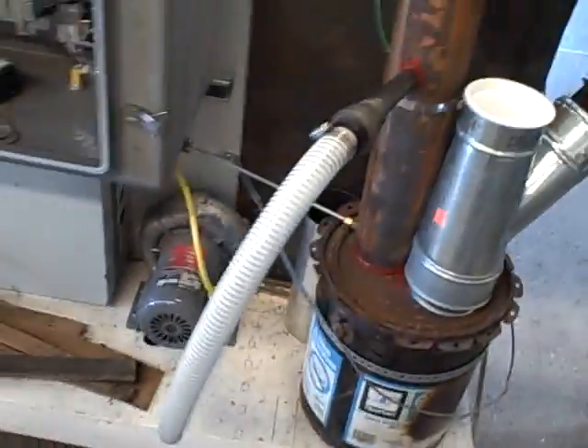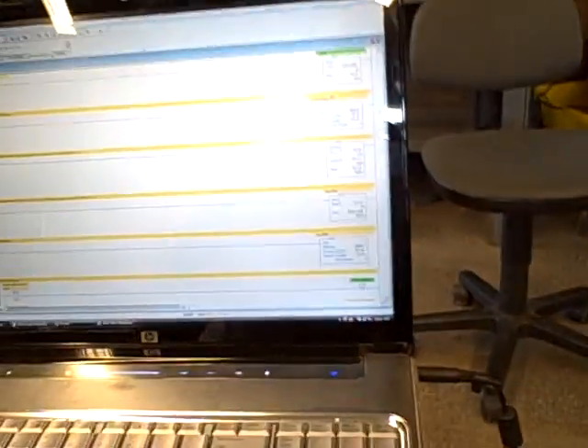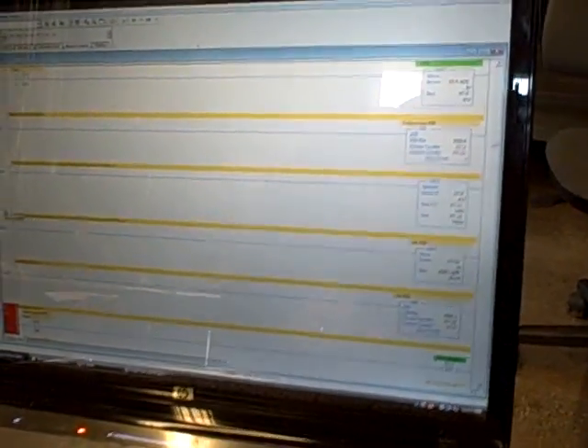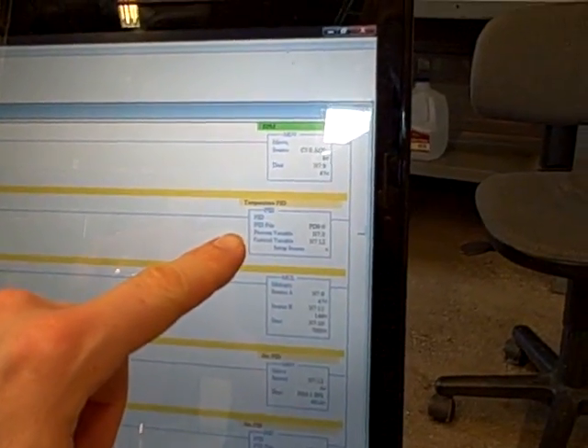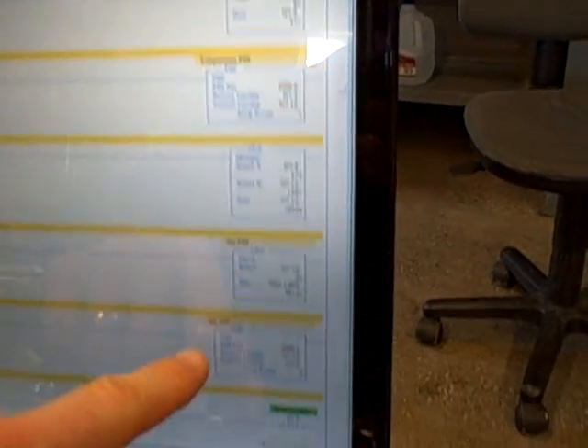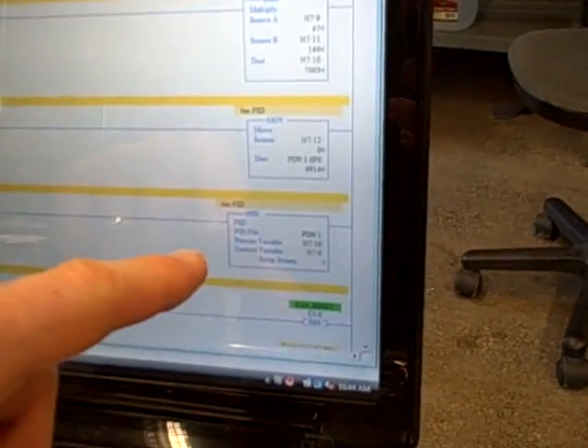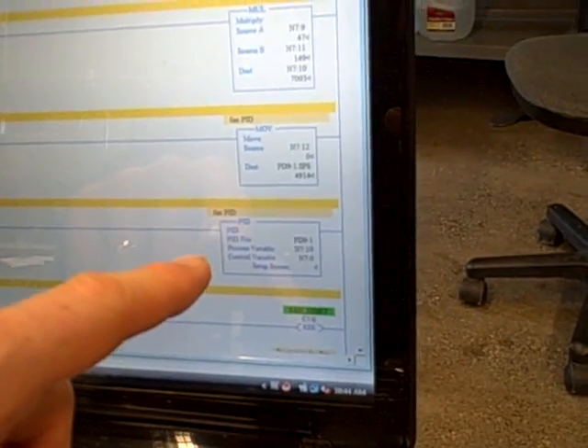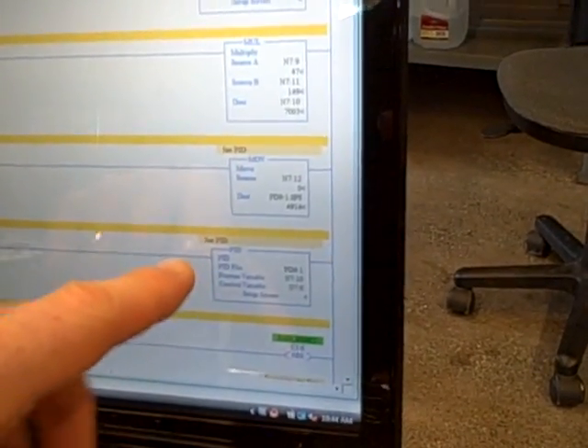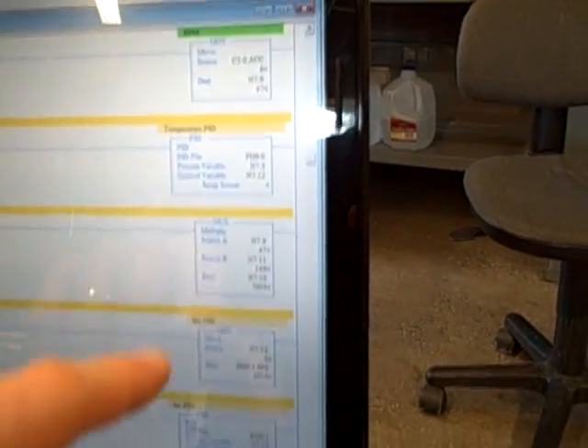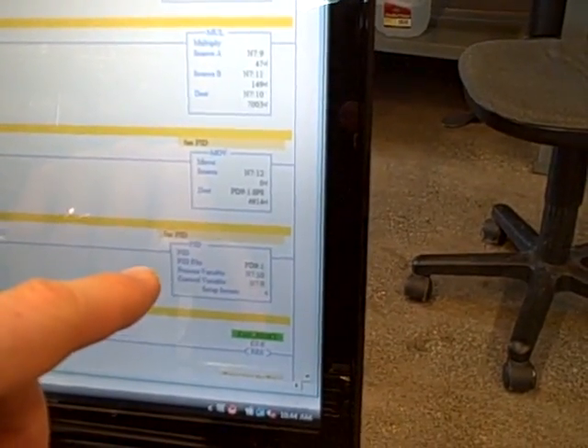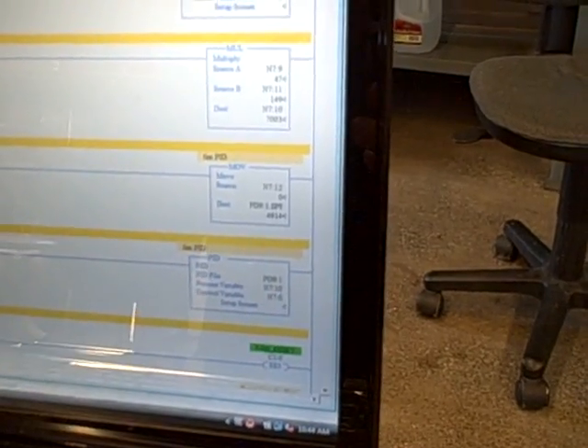That new restriction will hopefully be compensated before we see any impact on the temperature inside the furnace. To make the cascade control work in the PLC program using standard ladder logic, it's quite simple: we just have a PID instruction for temperature and a PID instruction for air flow. We want temperature to be the master and air flow to be the slave, which means the output of the temperature controller must become the set point for the air flow controller.